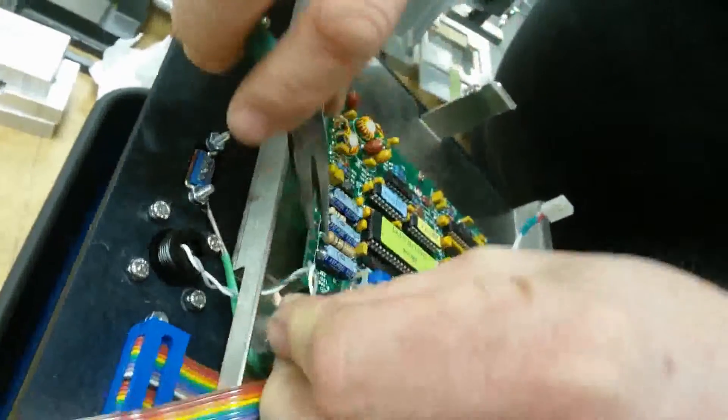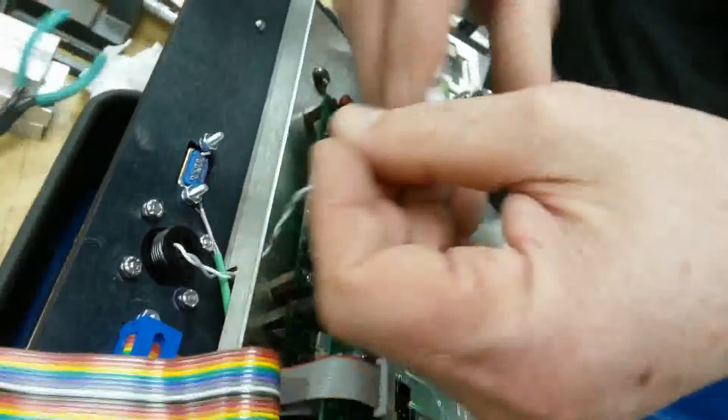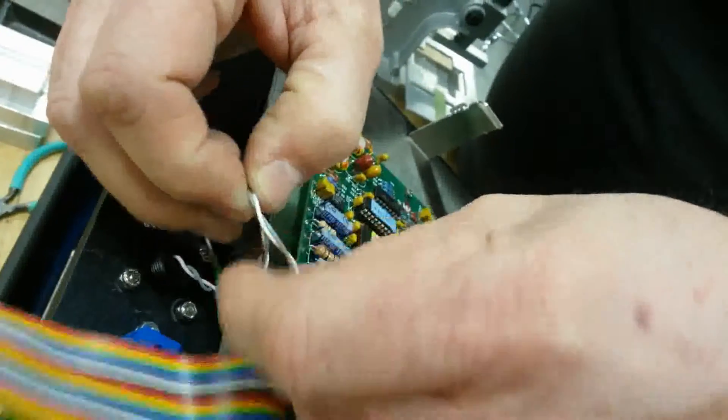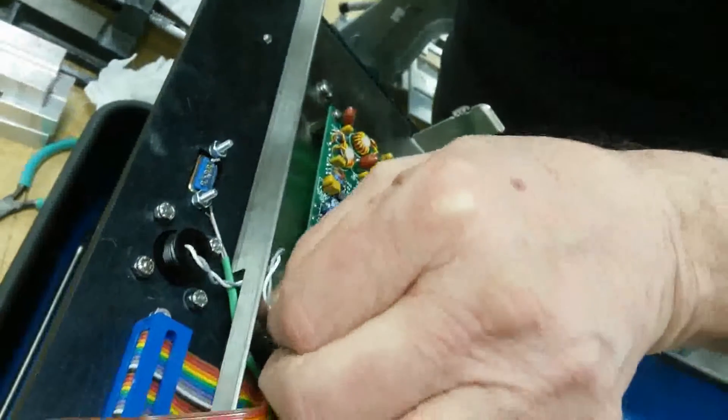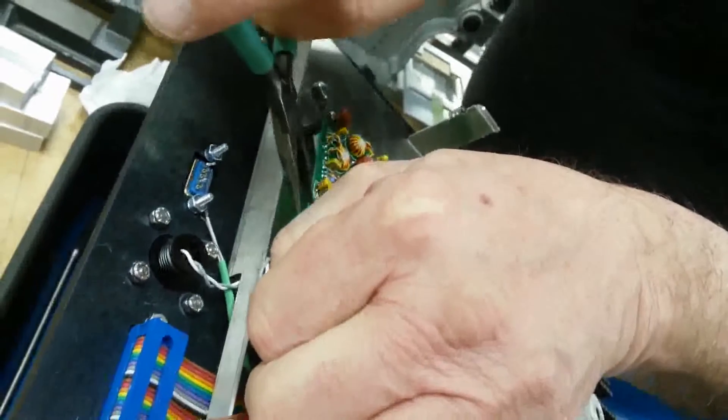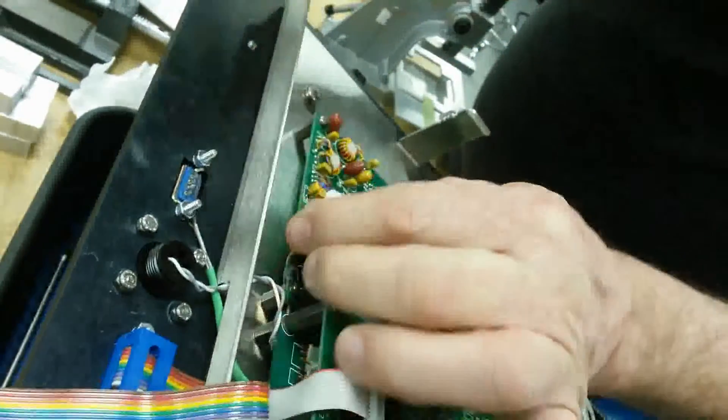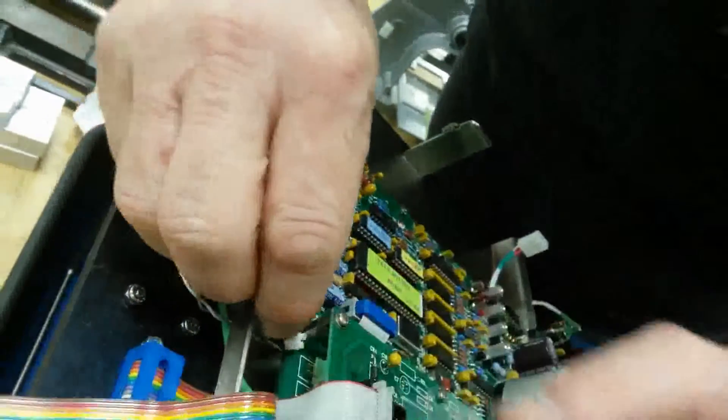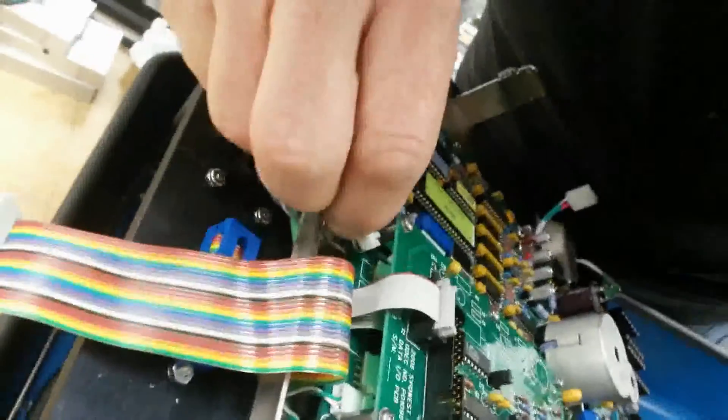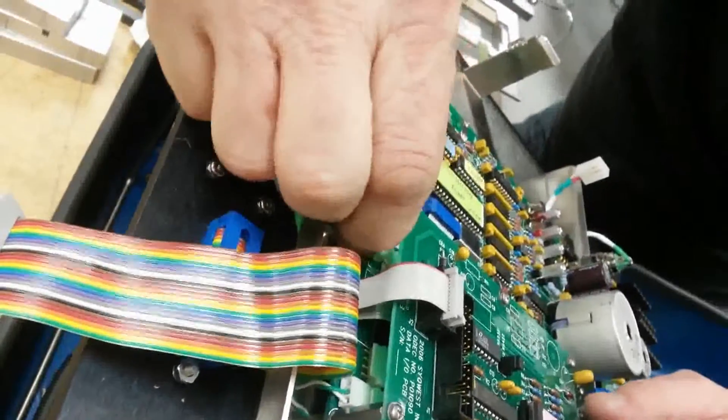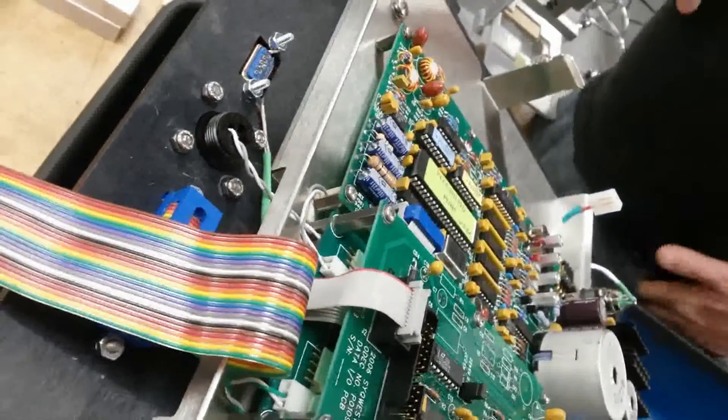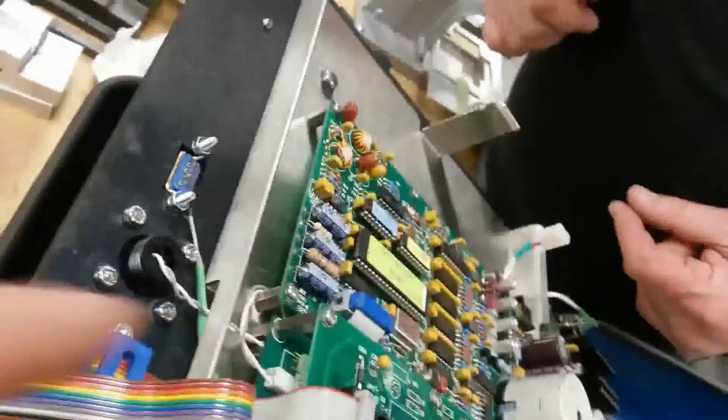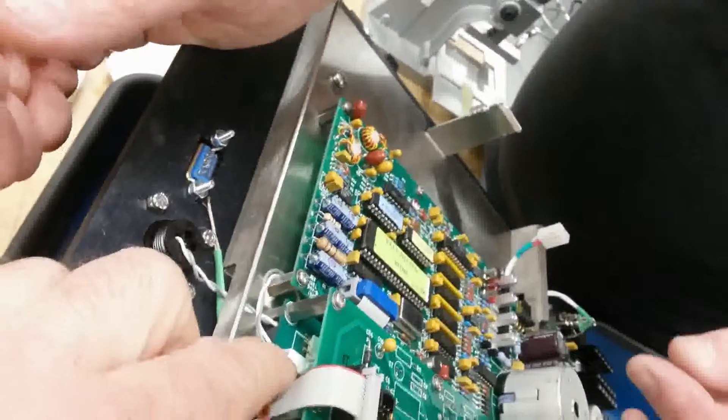And now Gary is just putting the fixed mark switch, little two-pin connector. He's just cut the cable twisted around the standoff so it doesn't get pinched when you close the chart. And then that goes into the two-pin header on the CPU that's furthest away from the chart paper. Okay, correction on that, it goes into the two-pin header which is second over. The first one's a three-pin, the next one's a two-pin. That's where the mark switch goes.